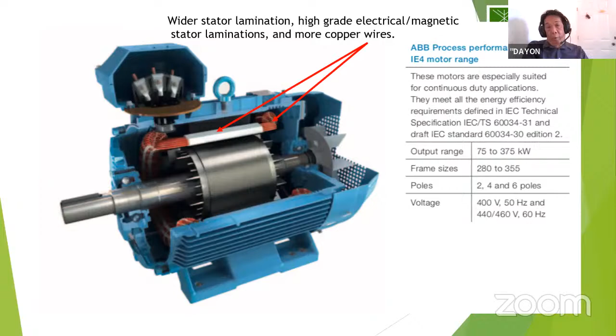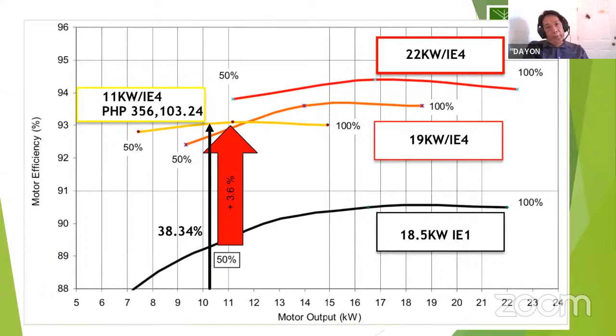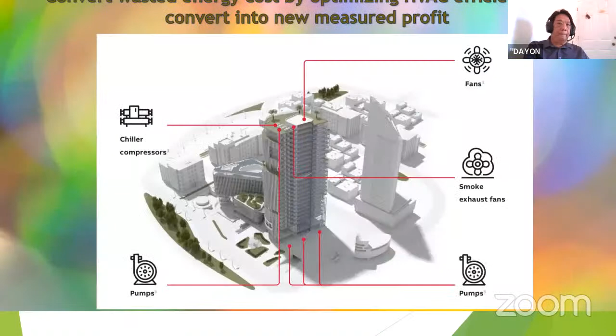So what I did is, okay let me check, sabi ko. So with this, almost 50% ang load niya. So from 18.5 kilowatt IE1, I would rather use 11 kilowatt IE4. Ang investment cost is only around 350,000. So with that, ang life sa motor mo dugay, and then you can reduce your energy cost. So this is the concept behind.